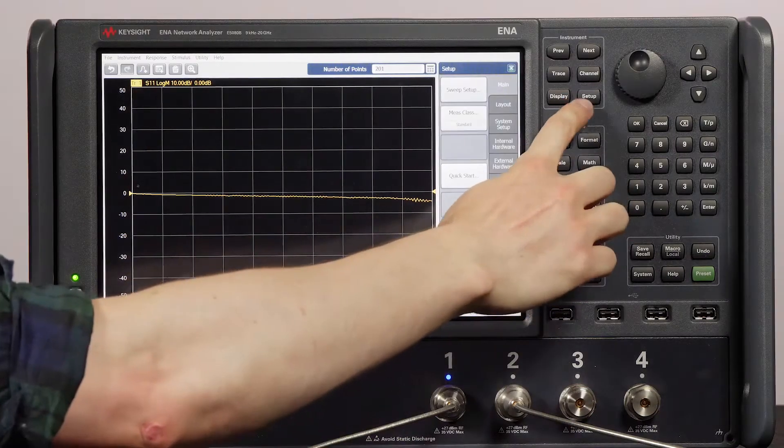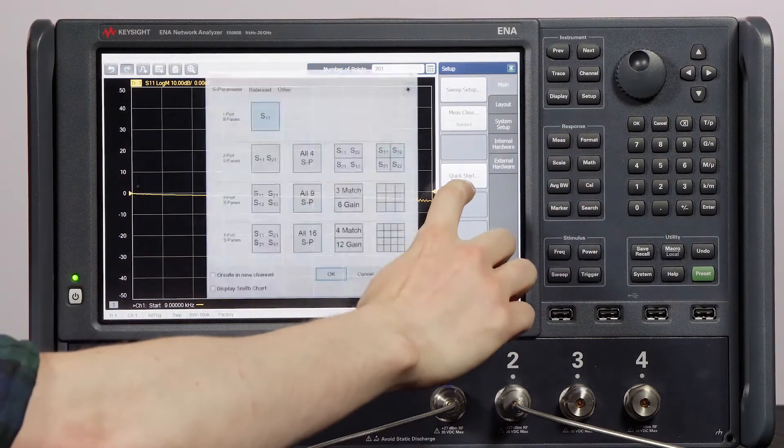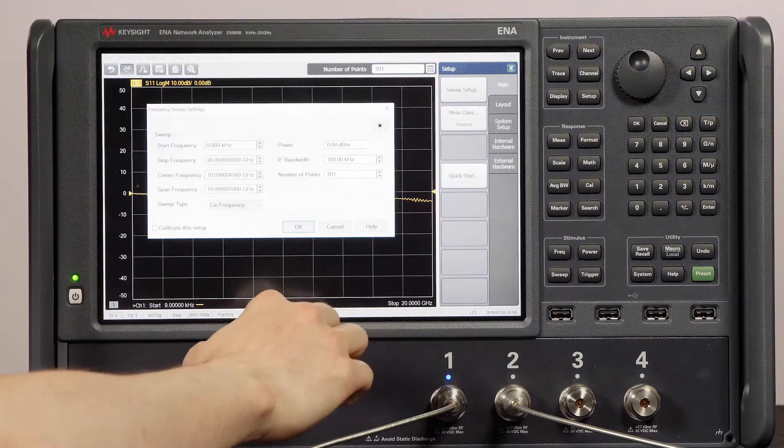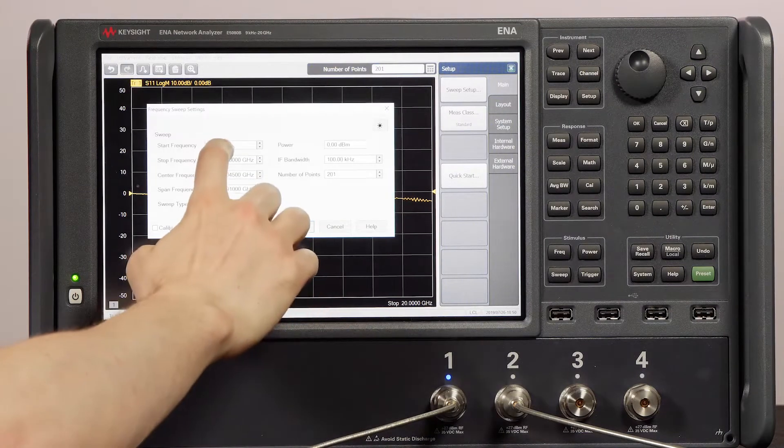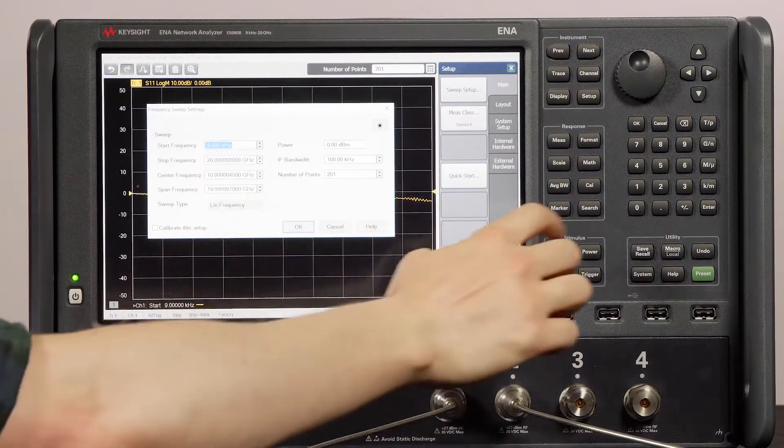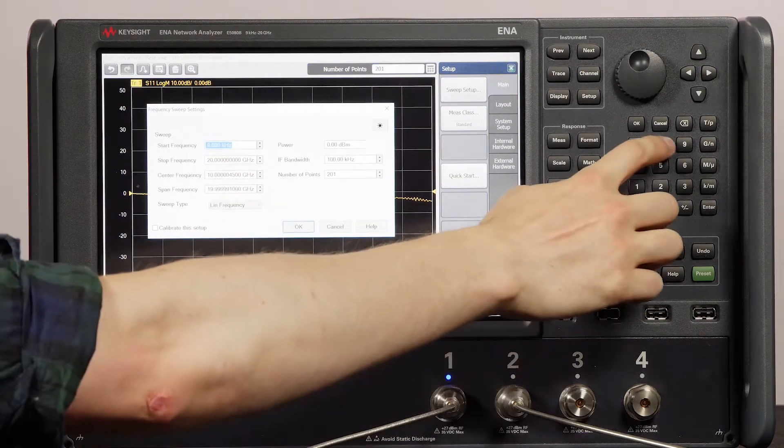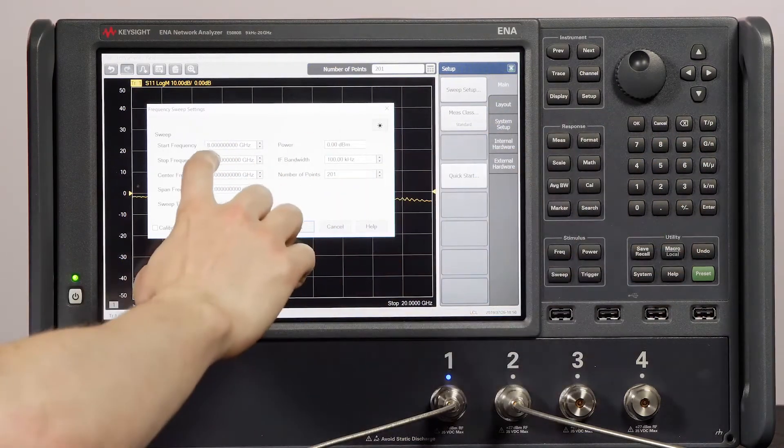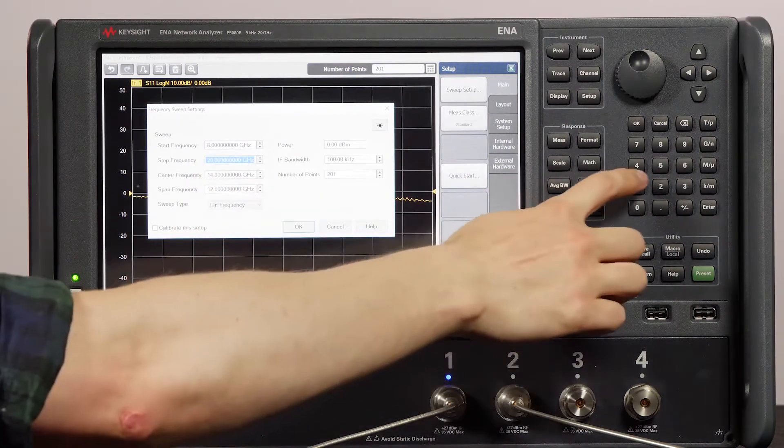I'm going to go into quick start to set up my measurement. We'll start with S11. Here I can input the start and stop frequencies, the sweep time, and an IF bandwidth of 1k hertz.